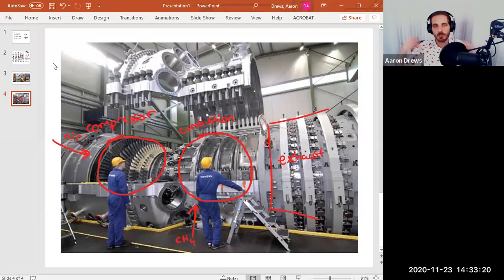That's what would then go off to the catalytic converter that they have at the plant that would clean it up and then eventually run it through the boiler so that they can get the cogeneration. They get electrical power directly from this turbine as it spins. The mechanical power of the spinning is converted to electrical power through a generator. And then our other element of cogeneration is the hot exhaust coming out here. So we should note that this is very hot. They usually don't pull it apart like that. If you are standing in front of it and it's operating and it's pulled apart like that, you probably won't be standing there too much longer because something terrible has happened. But they do take it apart and clean it every once in a while.